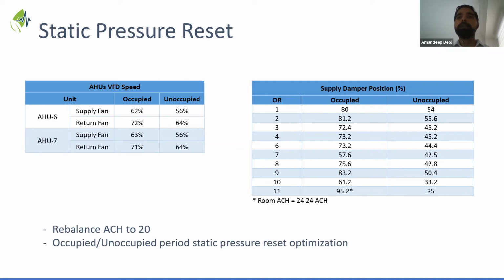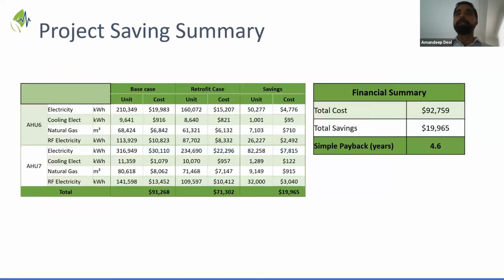around rebalancing those systems to match the CSA requirement, which is 20 air change rates, and then having occupied and unoccupied static pressure resets on those modes. This is a lesson we're currently seeing within all of these hospital projects: it's about optimizing those projects and, given the opportunity, working on those items.